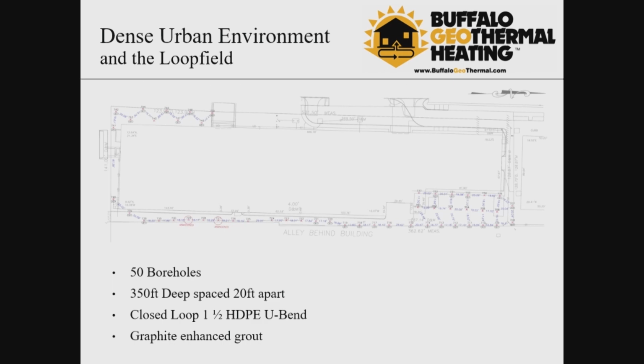The location in the dense urban environment within the Pierce Arrow factory complex required an innovative loop field design. We opted for 50 boreholes with a depth of 350 feet. Our original design was 500 foot deep. However, we encountered multiple gas pockets and saltwater pockets at about 380 feet.